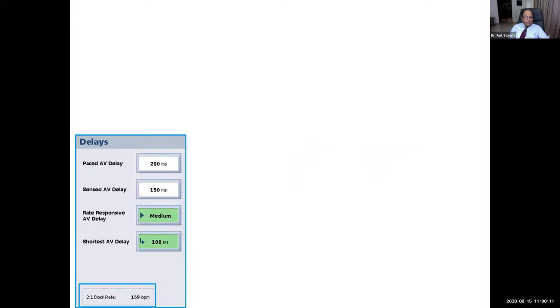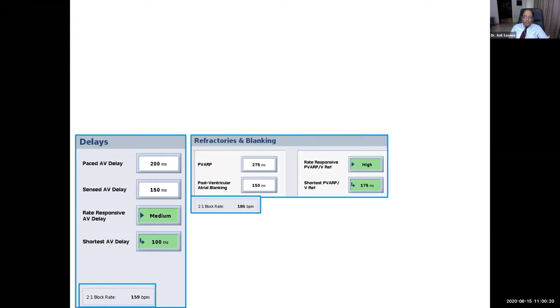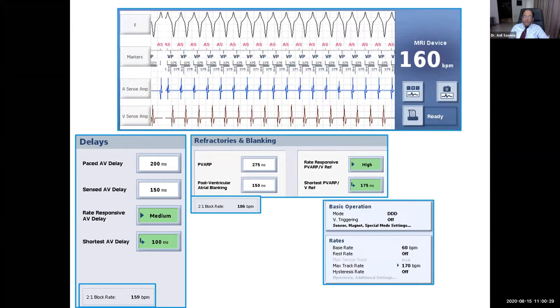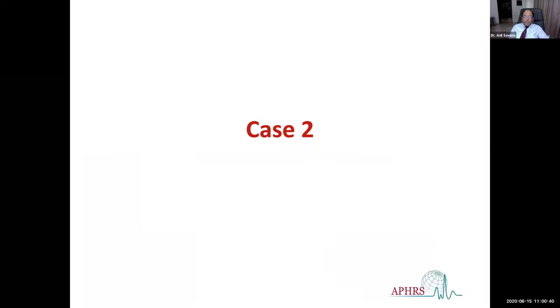So this patient can be programmed with a shorter AV delay, medium and rate responsive, so the minimum AV delay will be about 100. We can program the PVARP also to automatic rate responsive PVARP, with the shortest PVARP programmed to 175. That will allow tracking of a heart rate of 160, and we can see when the patient exercises again, there is 1-to-1 AV conduction or response, so the problem is solved.